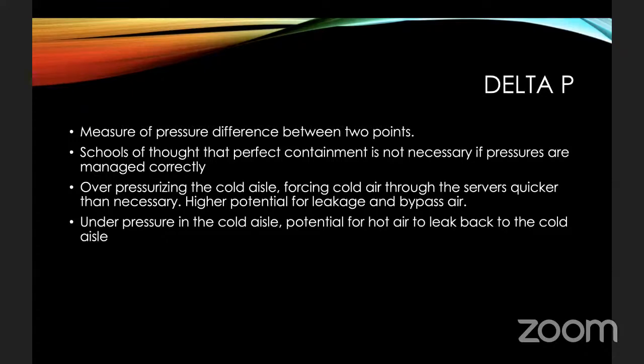First of all, you've got the laws of thermodynamics, where two densities of liquids or airs do not want to actually mix. And secondly, you've got the basic physical principle that the hot air is not going to flow into the cold aisle if the cold aisle is at a higher pressure, because the cold air will be pushing into the hot aisle, which is a separate issue. You don't want to be losing cold air into the hot aisle. You want that cold air to be going into the servers. The point is that the air will not actually mix, as in hot air coming into the cold aisle. So if you make sure the pressures are correct and balanced properly, then small leakages or small gaps in your containment shouldn't be an issue.